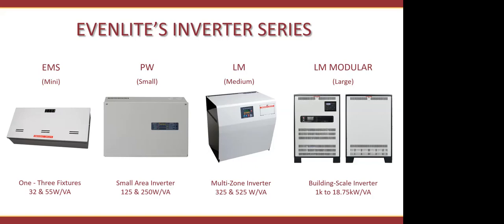There's a lot of discussion. It's not an easy answer to say, can we specify 250 watts on a 250 watt inverter? It may seem like a simple question, but it's not a simple question. And here's why. Can our 250 watt inverter supply 250 watts for the 90-minute period? Absolutely. Matter of fact, our 250 watt inverter would supply 250 watts for more than 90 minutes, but it's rated for 90 minutes. So we really have you covered there.